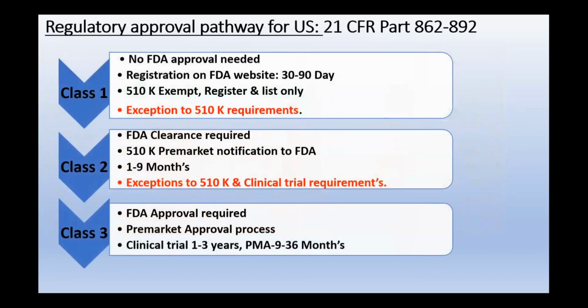This is the regulatory approval path for the USA. For class 1 medical devices, no FDA approval is needed. Only registration on the FDA website 30 to 90 days prior is needed. Along with that, the 510K notification, that is the predicate device notification, is exempted because there is no risk associated with class 1 medical devices which could seriously affect the health of users or the quality of life of the user. That's why the 510K requirement is exempted for class 1 medical devices.